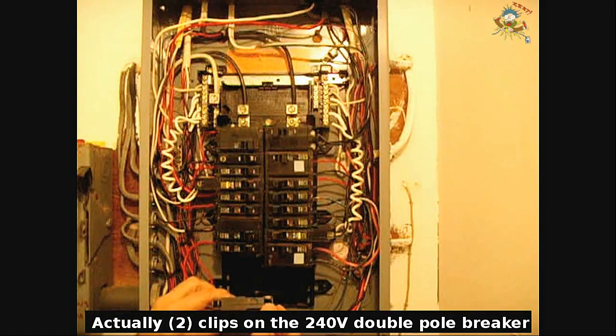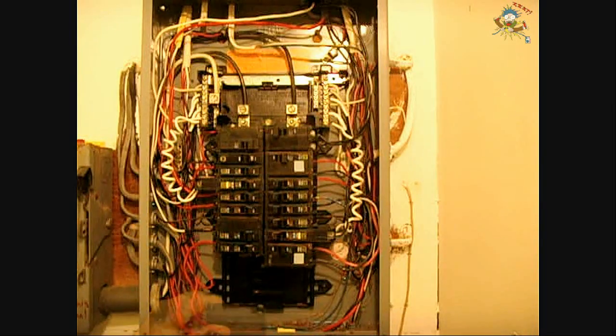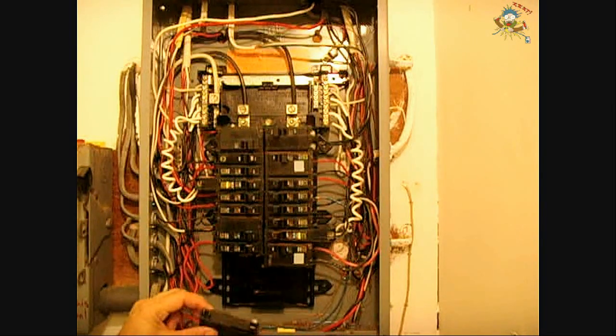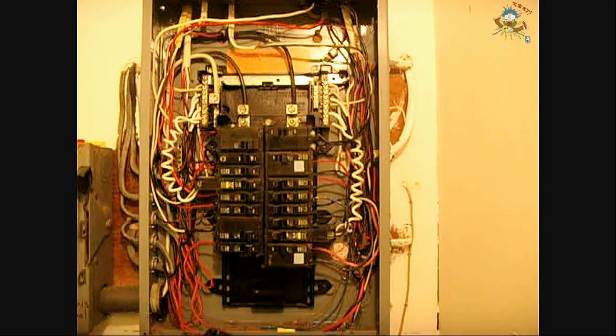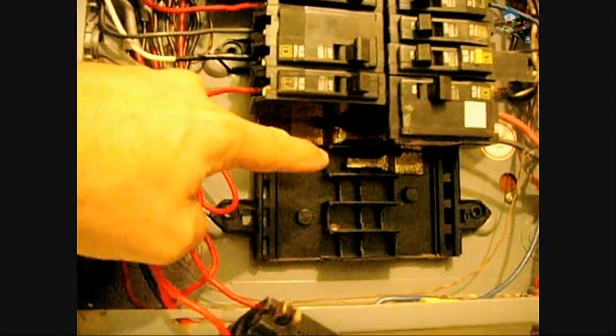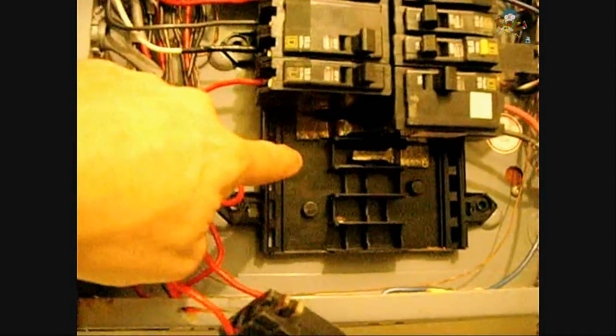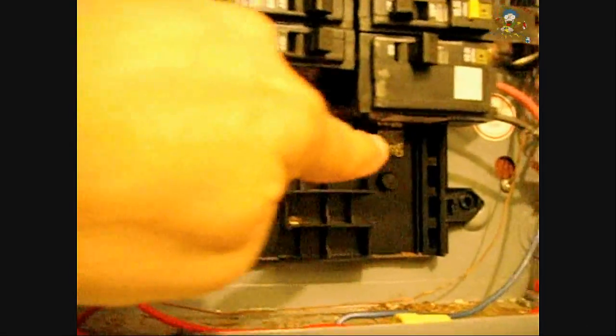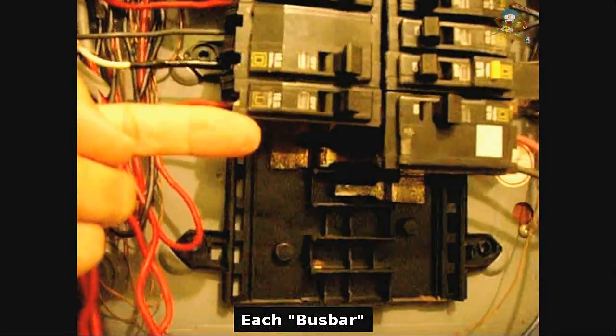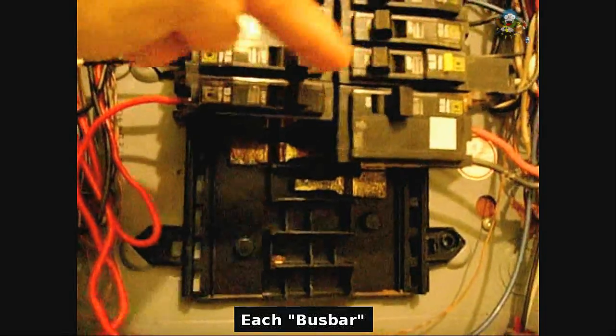You're going to want to look very closely at the clip, see if there's any burned marks or if it's pitted up. And if you find one where you notice that this looks a little burned, what's going to happen, let me take the camera a little closer and show you. Alright, right there is a bus bar. You can see this one here is separate from that one over there. This one goes all the way up to that lug, and that lug there goes all the way down and ties into that one right there you're looking at that connects that way. They alternate. There's one from that lug going this way, and there's one from this lug going that way. The next one up will be coming from this way.